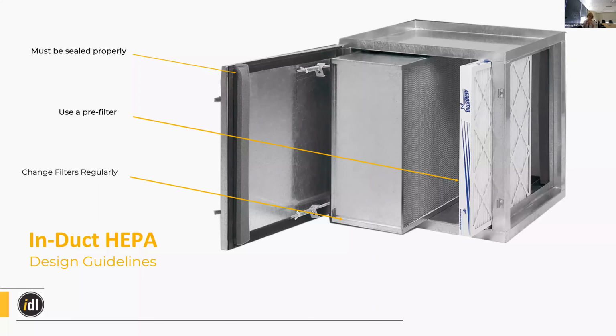You're just going to get that much more particulate getting on the sides, just like the MERV. It's going to go right past if you don't have it sealed right, meaning you want to tape or gasket, or just make sure that the system is exactly sized for that HEPA filter. And again, just changing them.